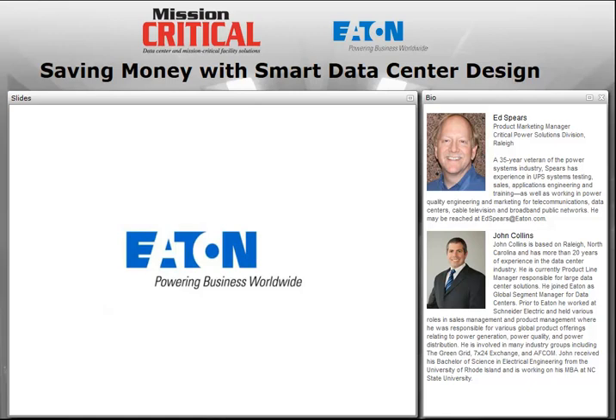So as with every large UPS that we sell or market, we strongly recommend the use of a wraparound or maintenance bypass circuit. So each of the primary UPSs would have a traditional wraparound bypass, otherwise known as maintenance bypass. I did not try to put that in the drawing just for simplicity purposes, but that would allow me to continue to feed catcher power to the critical load while I completely de-energize primary UPS number 1. Everything in that UPS is completely electrically dead and can be serviced and replaced. In fact, the entire UPS could be replaced if necessary without disrupting power to the critical load.